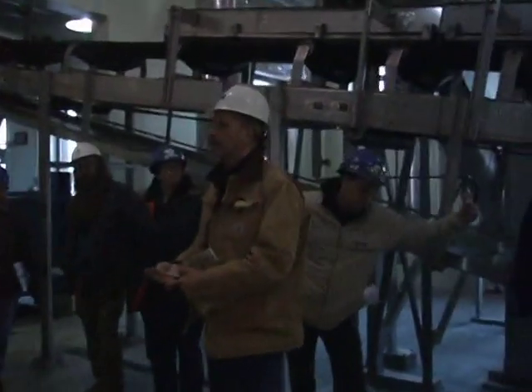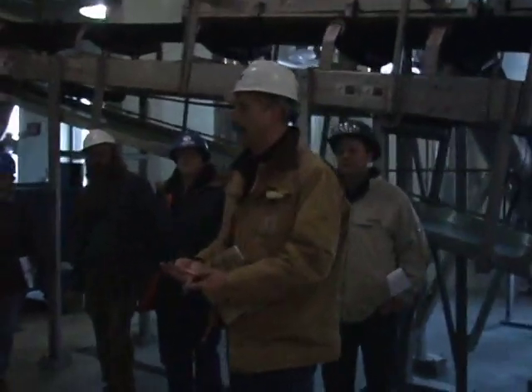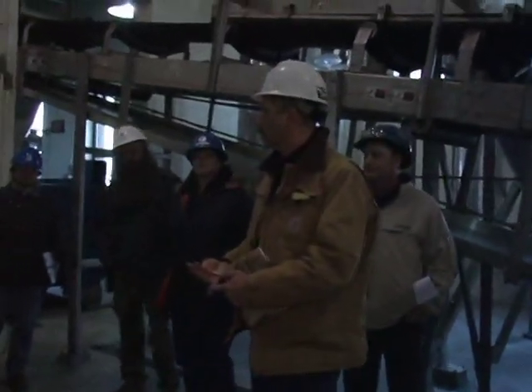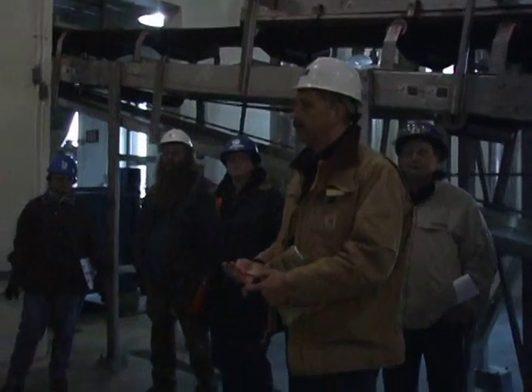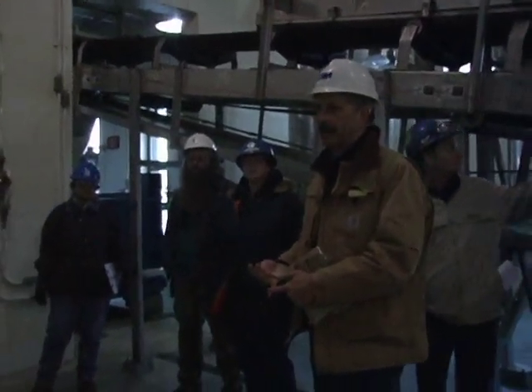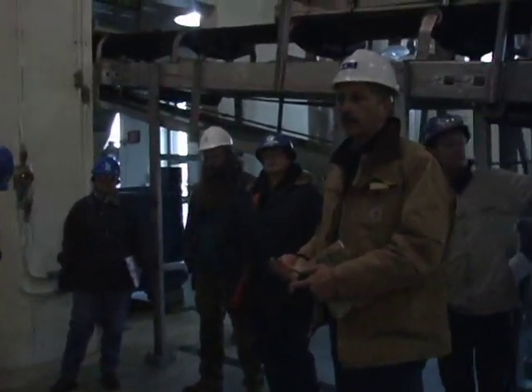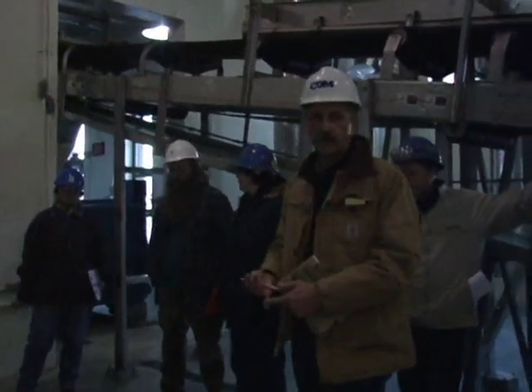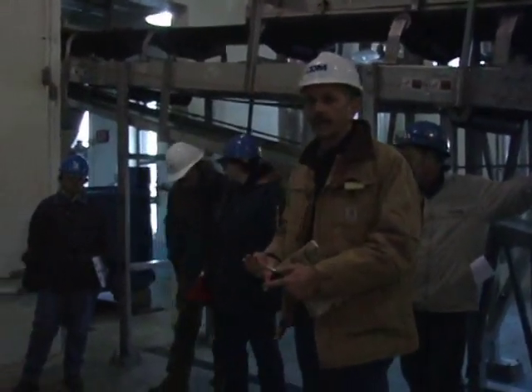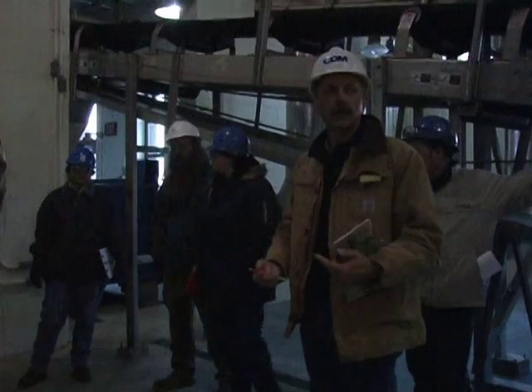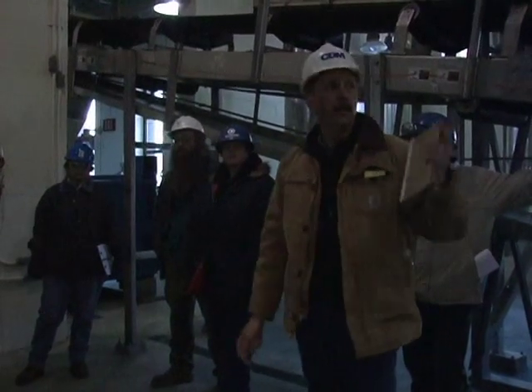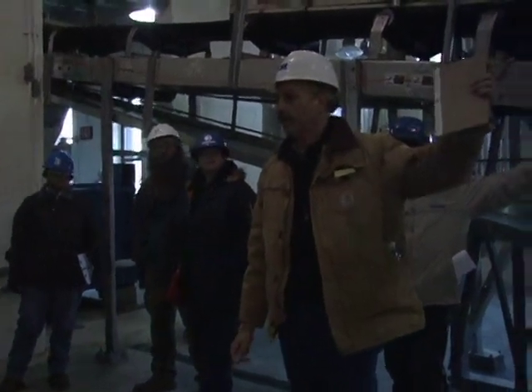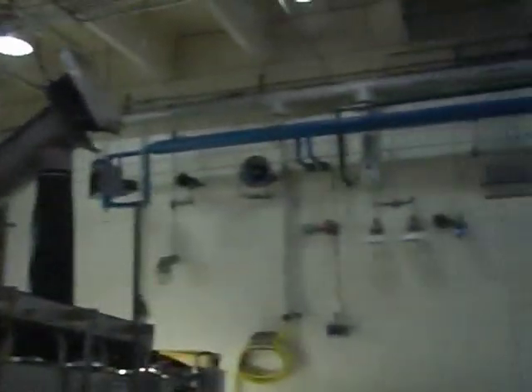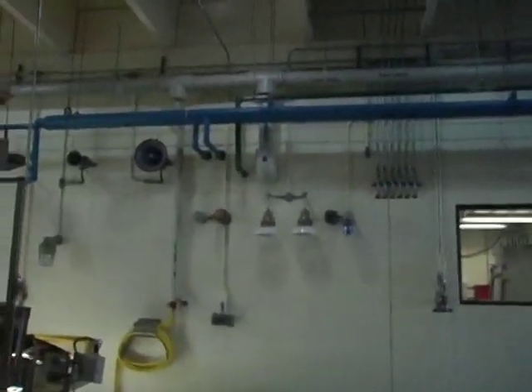At this point you will not know whether it's a hydrogen sulfide or a lower explosive limit. Those values can be monitored through SCADA, so you can determine which gas you're dealing with and which probe is in question. But you will get an alarm indicating that you've got a problem in the building. Again, you've got a blue beacon in here as well as a horn indicating that you've got a situation within the building itself.